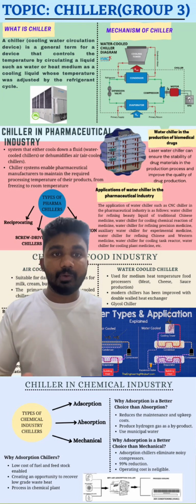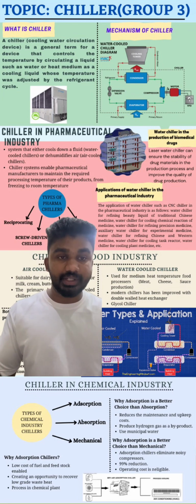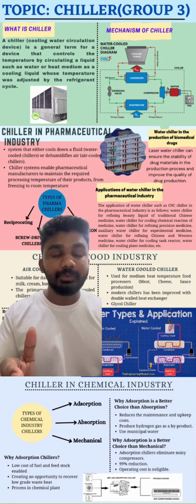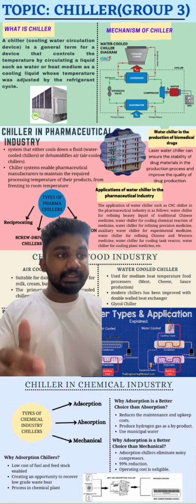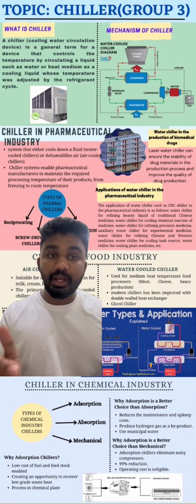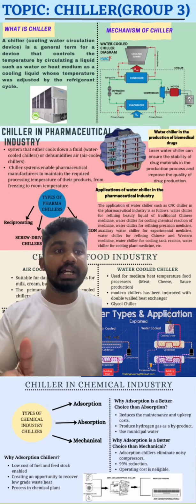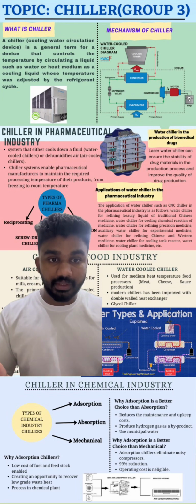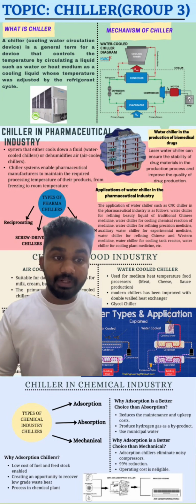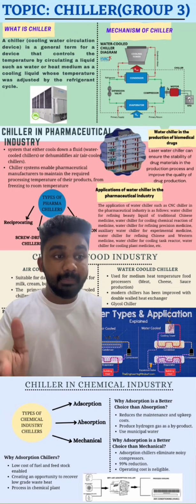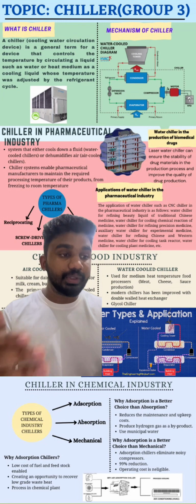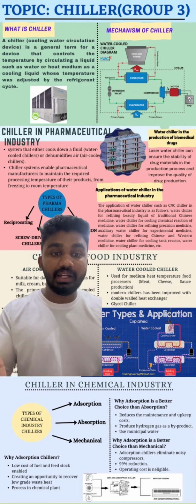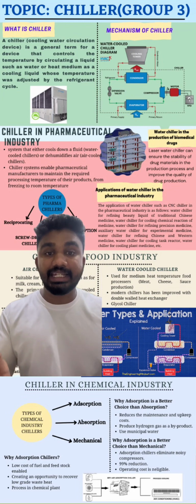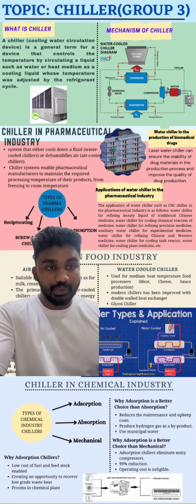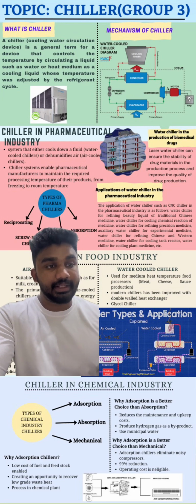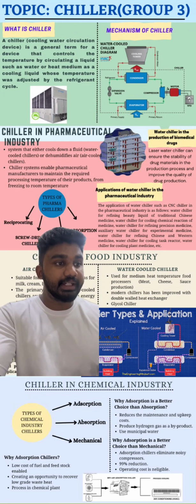Okay, now let's see why an adsorption chiller is a better choice than an absorption chiller. An absorption chiller produces hydrogen gas as a byproduct and also requires an expensive palladium cell inside the chiller unit to remove the hydrogen. But an adsorption chiller significantly reduces the maintenance and upkeep by substituting the corrosive salt desiccant with silica gel.